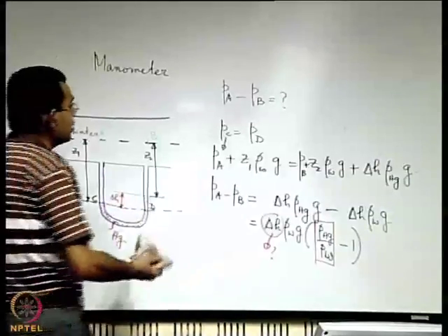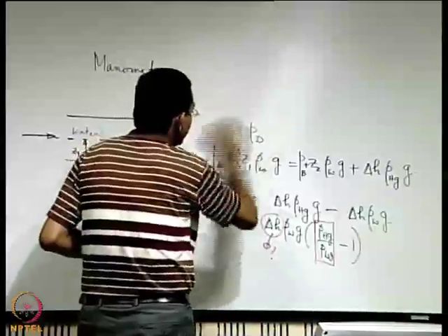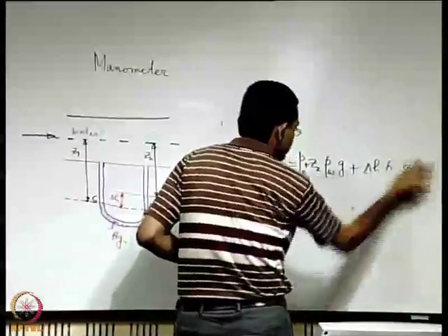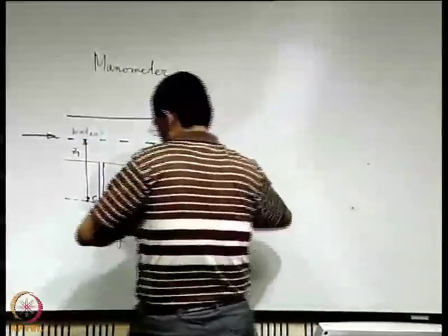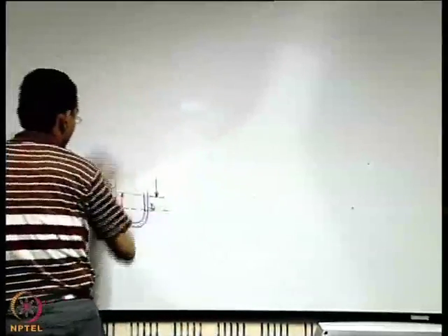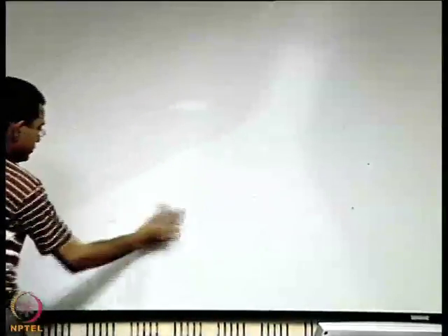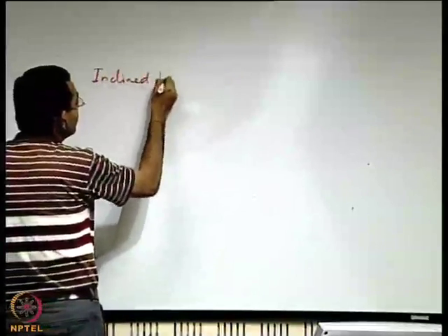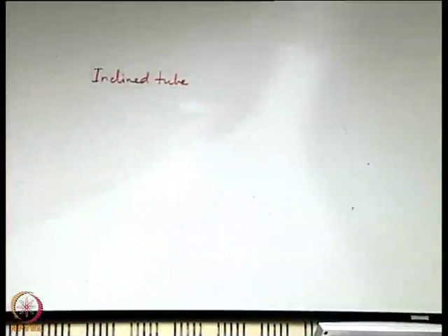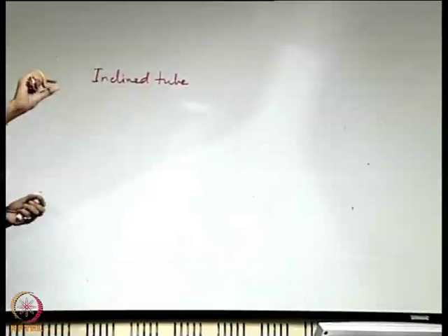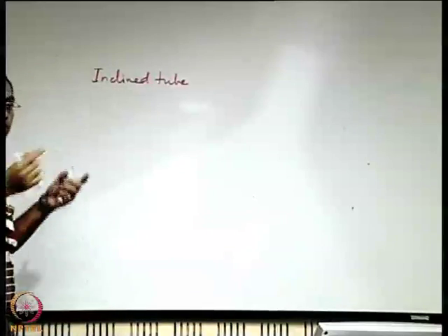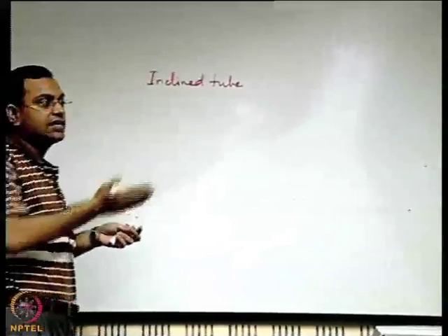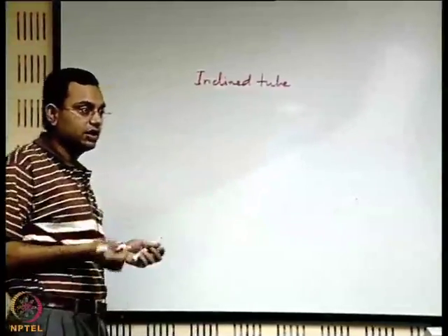The resolution of this device strongly depends on delta H, because if this is very small there can be a lot of reading error, which will magnify the error in determining PA minus PB. If delta H is quite large or magnified, it may be easier to read with greater accuracy. To achieve this, sometimes people use inclined tube manometers.